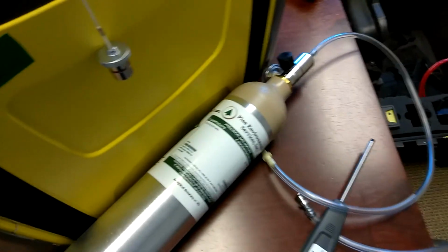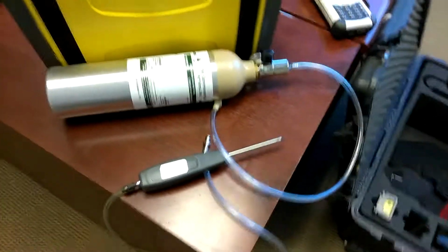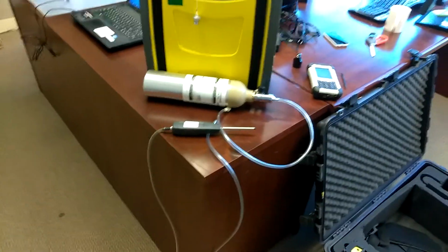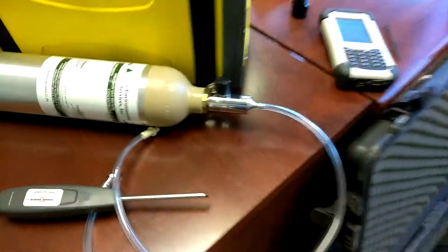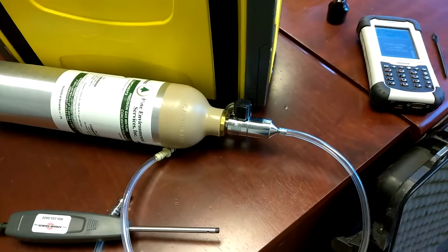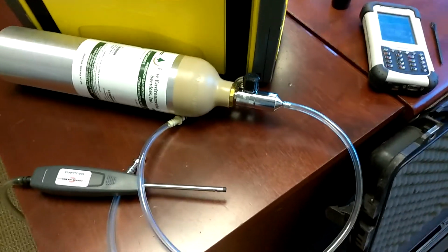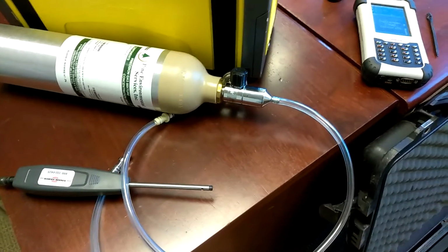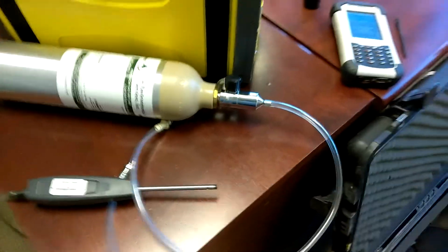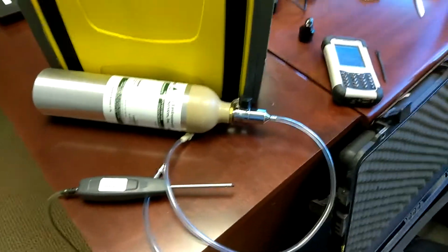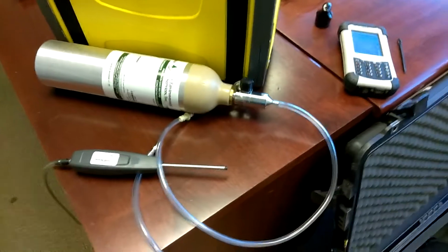They say you can use zero air or instrument air as well, although I would recommend that you use nitrogen for this because that is the gold standard. So we'll get a bottle of nitrogen. This regulator is 2 liters per minute. Actually, this one in particular is 1 liter per minute because that's what I was sent with the rental equipment, but 2 liters is ideal. It can go to 3. I have been told 6 is too high, so better lower than higher.